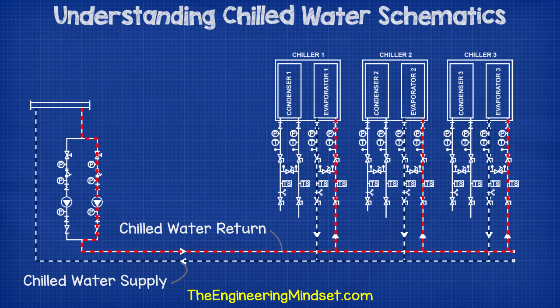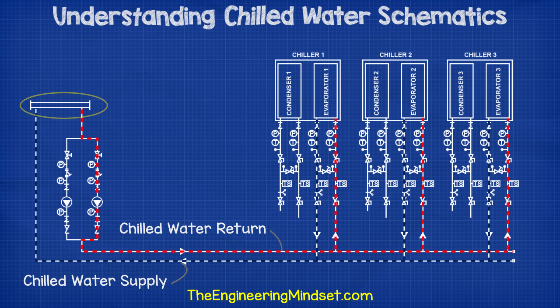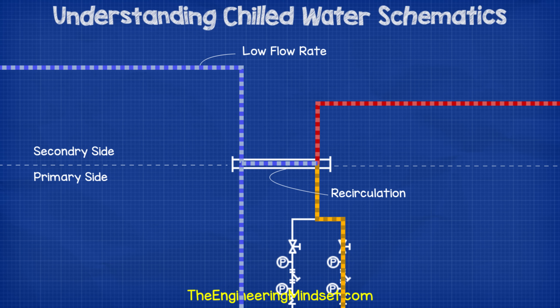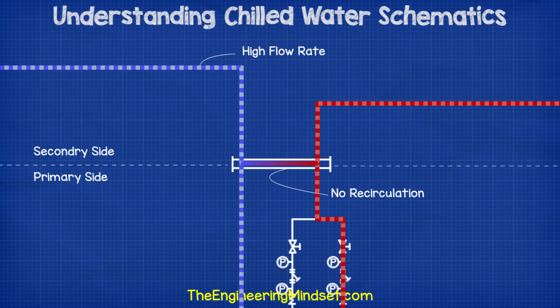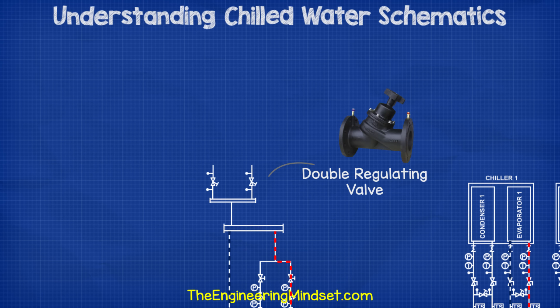Notice there is a common header here between the flow and return lines. This separates the system into primary and secondary loops and allows a constant flow rate in the primary side, which the chillers prefer as they require a minimum flow rate. It also allows a variable flow rate in the secondary side as the cooling load changes. The chilled water is generated and circulated in the primary side loop. The secondary side loop will pull the chilled water out of the header to cool the building and will then dump its warm return water back into the header. If the flow rate in the secondary side loop is low, then some of the chilled water will flow into the secondary loop and some of it will recirculate back to the chillers. If the flow rate is high in the secondary side loop, then all the chilled water will flow into the secondary loop and the return line will flow straight back to the chillers.